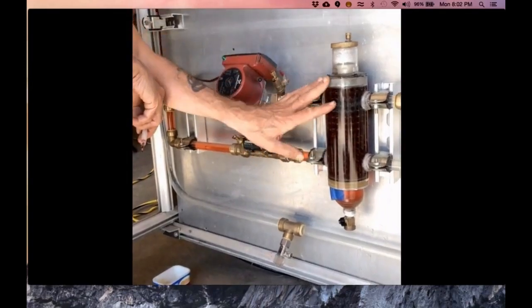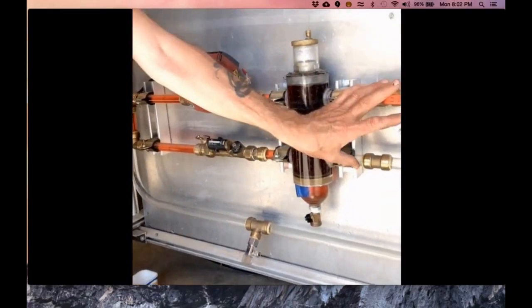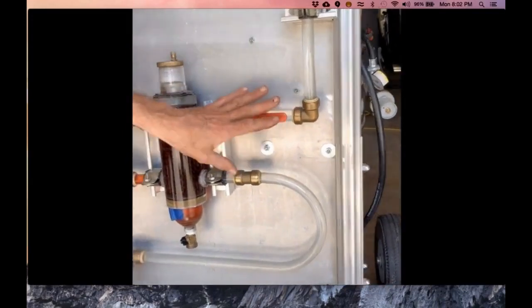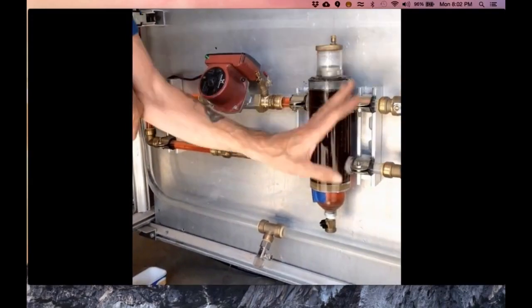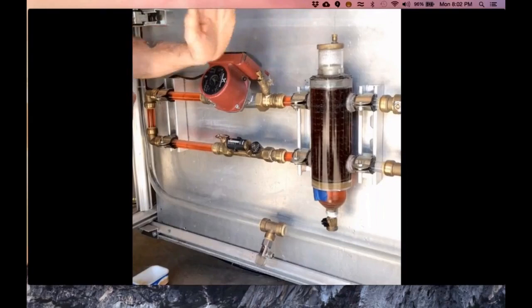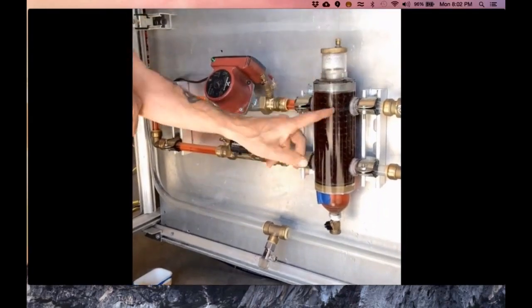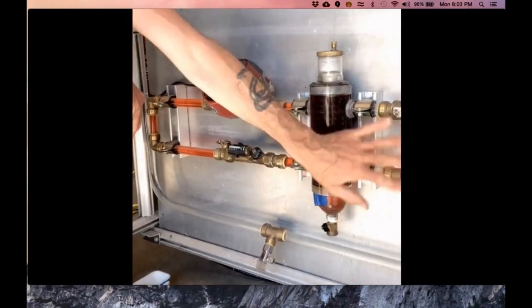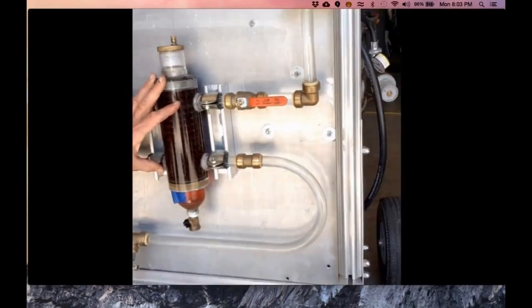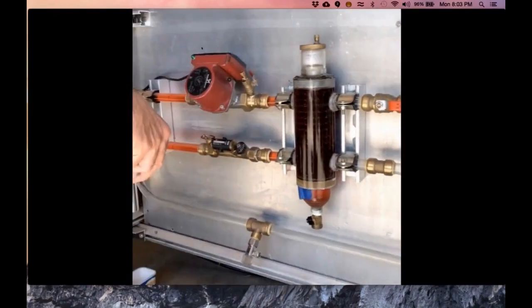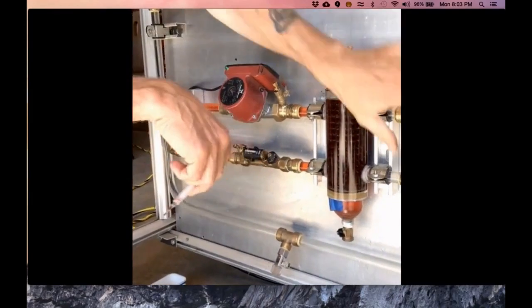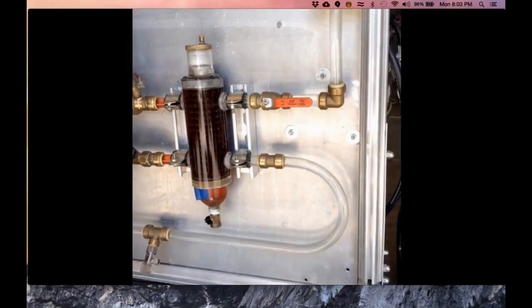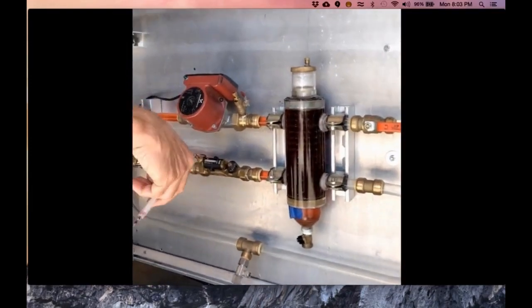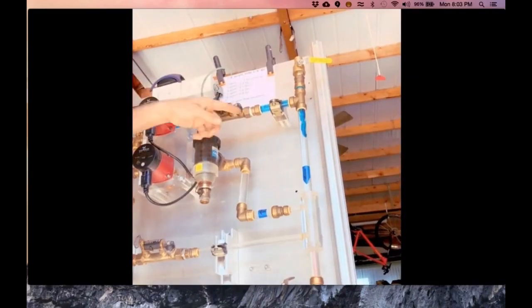So let me shut this pump off, then I'll go and put some blue in this side. This one off, this one running, and you'll see how the blue, it'll probably turn to purple a little bit. It's going to mix with the red, but that's going to give you an idea how that separation works inside of this chamber. You can see no red coming over here, and the circulator pump's been running now. So turn that one off, and then I go up, put some blue into this side, the primary side, let's call this. Let's see what happens. You ready? All right, put the blue in here.